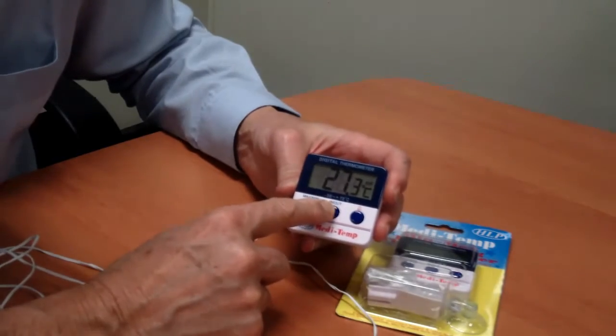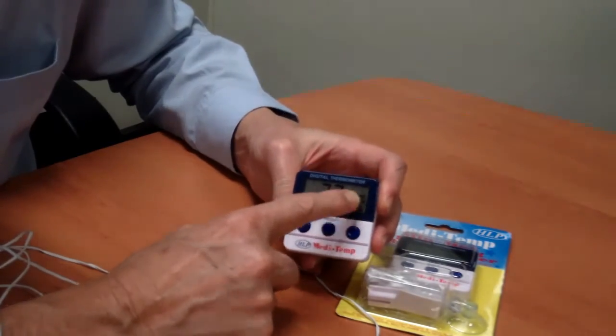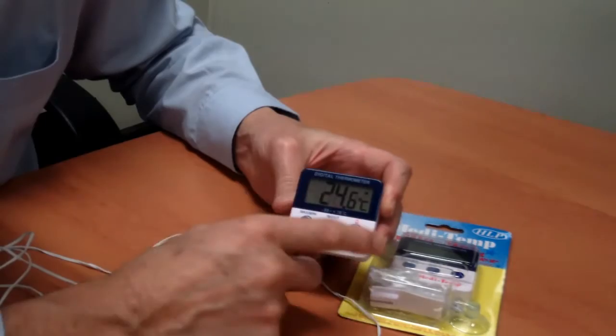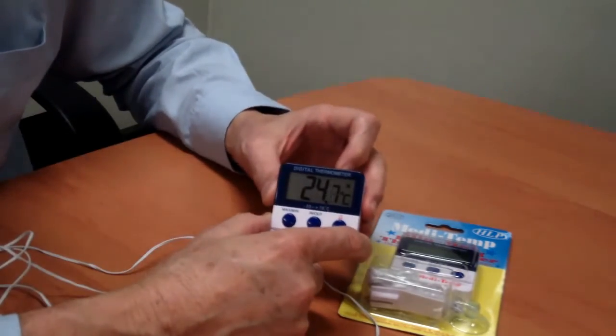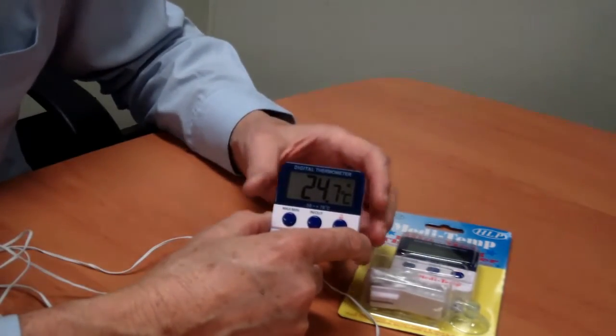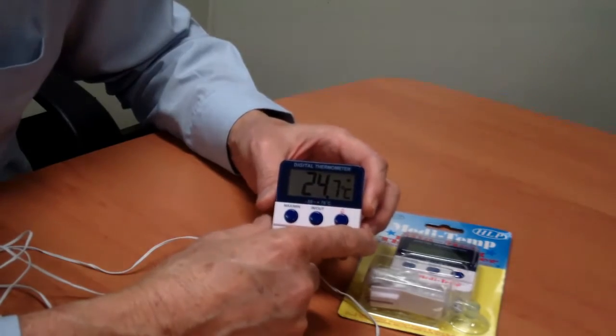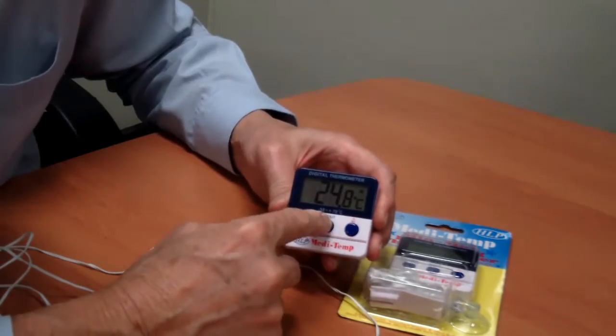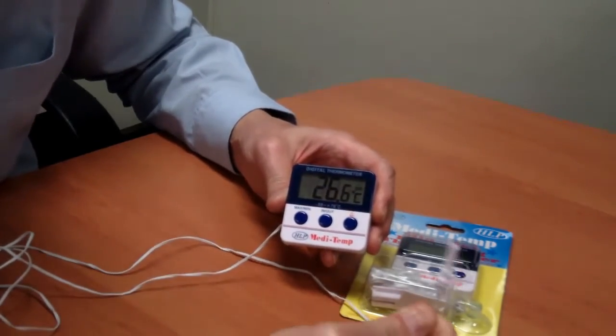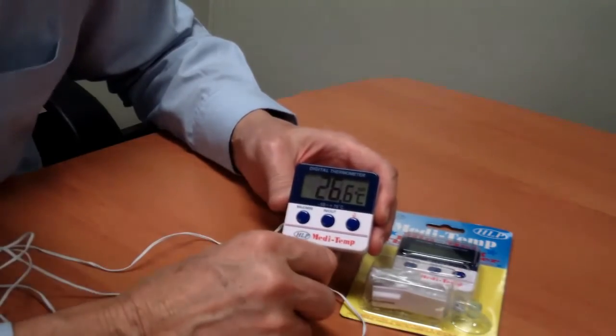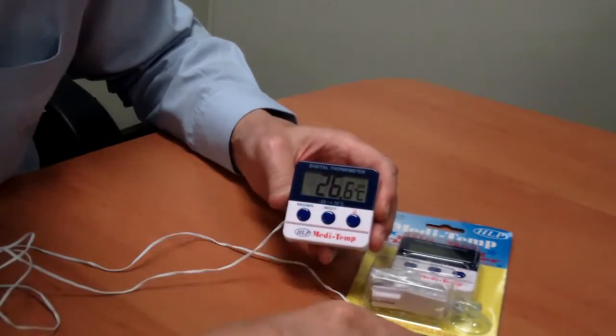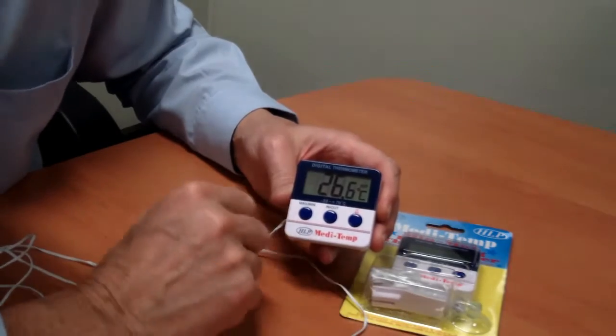And you can do that by the middle button. It says in, out. So now it says out. If I go in, it tells me the temperature of this unit. And it might be of interest to me if it was a room where I wanted to monitor the temperature. So out is on the wire, that'll be in the probe, and in is in the unit. Normally you'd leave it always on out if you're using it for vaccine fridges.